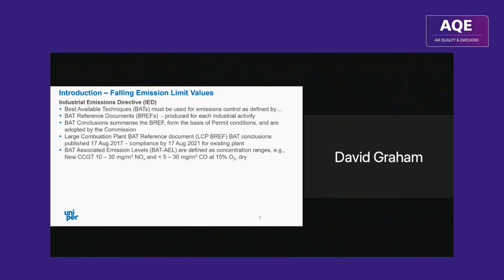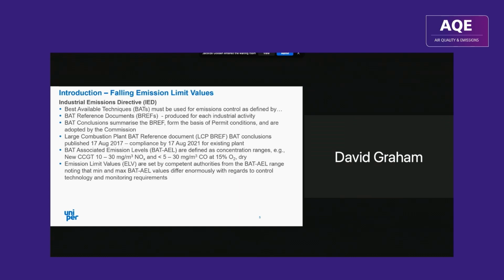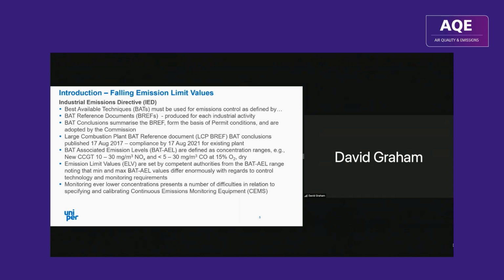And BAT-associated emission levels, BAT AELs, are defined as concentration ranges. So for a new combined cycle gas turbine, for example, the range is 10 to 30 milligram per meter cube NOx and 5 to 30 milligram per meter cube CO. So these are significantly lower than previously. Regulators set emission limit values from within that range in a given permit, and obviously whether they set it at 10 or 30 has a huge impact on the control technology that's required and also the monitoring requirements. And as Rod's pointed out, monitoring ever lower concentrations presents a number of difficulties in relation to specifying and calibrating CEMS.